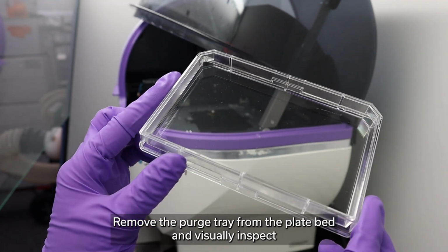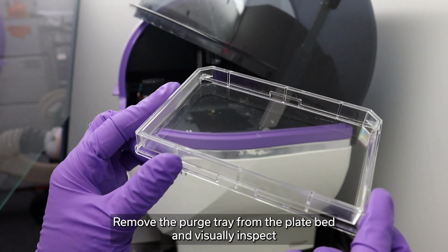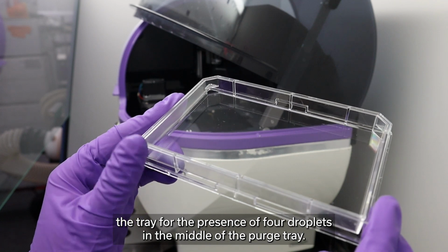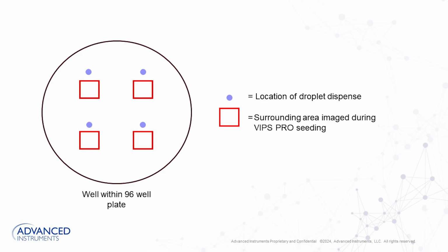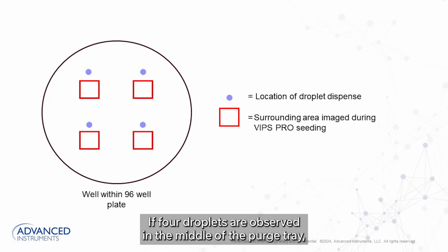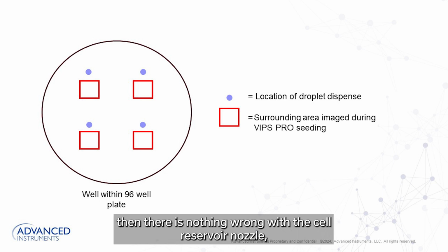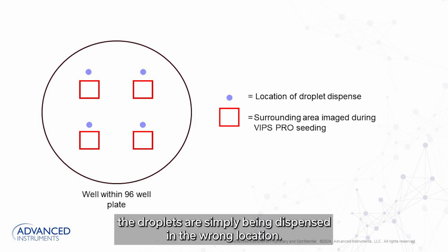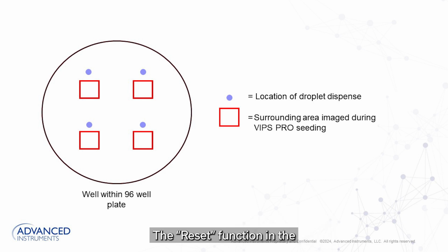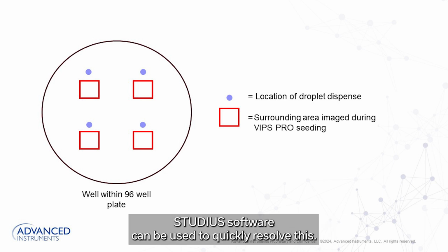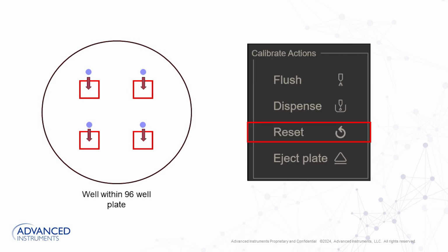Remove the purge tray from the plate bed and visually inspect the tray for the presence of 4 droplets in the middle of the purge tray. If 4 droplets are observed in the middle of the purge tray, then there is nothing wrong with the cell reservoir and nozzle. The droplets are simply being dispensed in the wrong location. The reset function in the Studious software can be used to quickly resolve this.